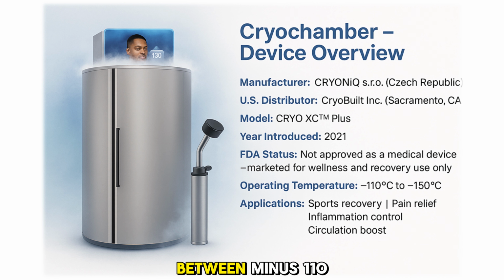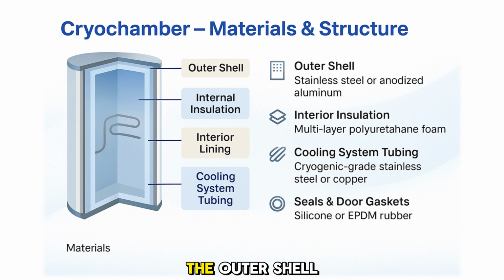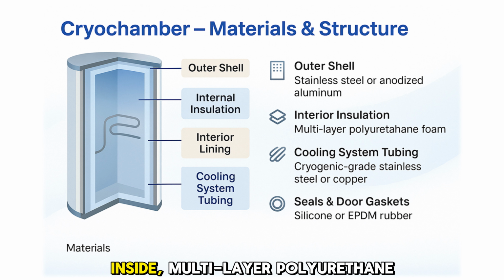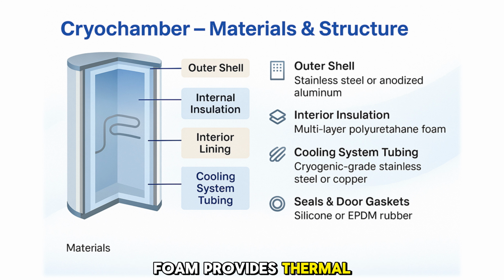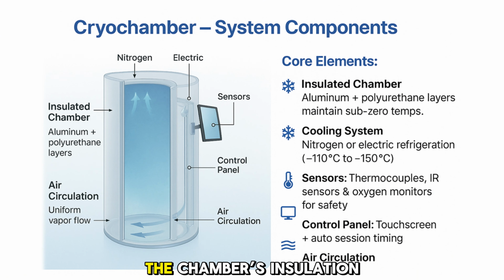The chamber operates between -110 and -150 degrees Celsius and is used for sports recovery, pain relief, inflammation control, and circulation enhancement. The outer shell is constructed from stainless steel or anodized aluminum. Inside, multi-layer polyurethane foam provides thermal insulation. Cooling system tubing is made from cryogenic-grade stainless steel or copper, and the seals and door gaskets are composed of silicone or EPDM rubber to maintain airtight integrity. The chamber's insulation combines aluminum and polyurethane layers to maintain sub-zero conditions.